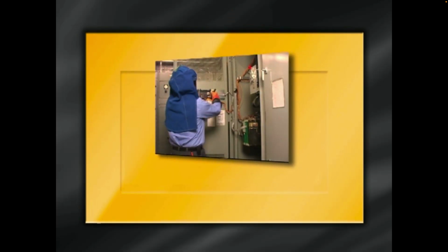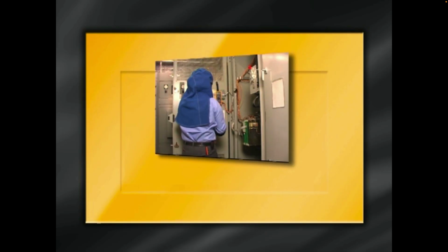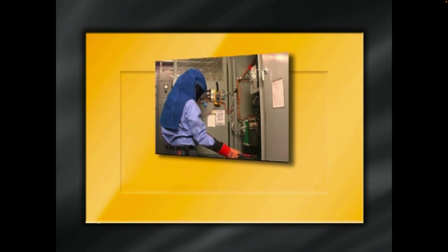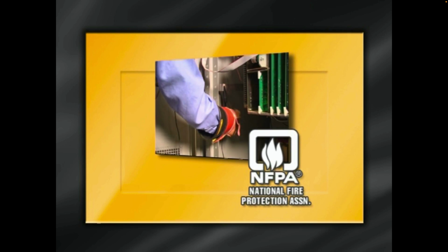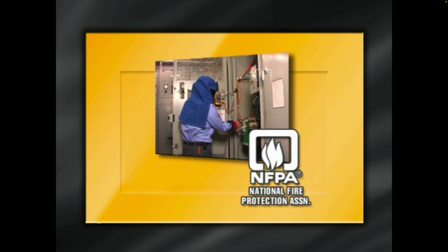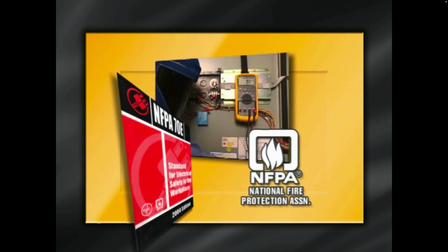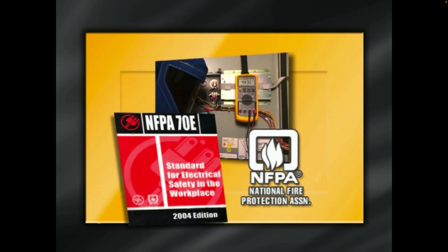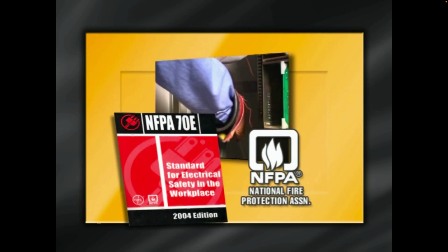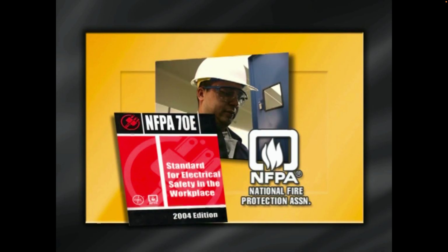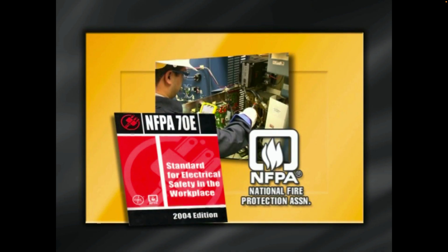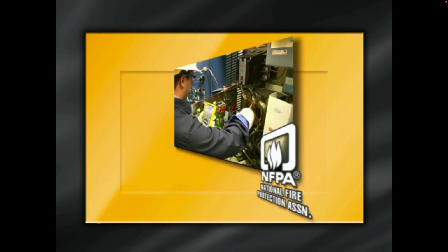In this video, all individuals shown making the electrical measurements are wearing personal protective equipment consistent with the standards established for the United States by the National Fire Protection Association, or NFPA. NFPA Electrical Safety Standard 70E sets categories of hazard and risk from 0 up to 4. As the work environment and the type of job become more hazardous, the need for protection increases. For example, work on a 600-volt motor control center would require varying levels of protection, depending on the job.